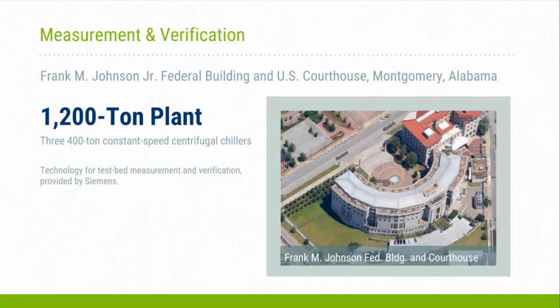So the chill water plant that's housed in the basement of the large arc radial building serves both buildings. The previous slide that we looked at actually has two sets of secondary pumps that distribute chilled water to both buildings. The challenge is the annex, which is the original building, the red tile roof, was never designed with any airside economizers, and therefore often requires cooling almost year round. The challenge that brings is low loads, and a lot of chill water plants that are constant flow have a very difficult time maintaining consistent or efficient operation. So those are some of the things, background.